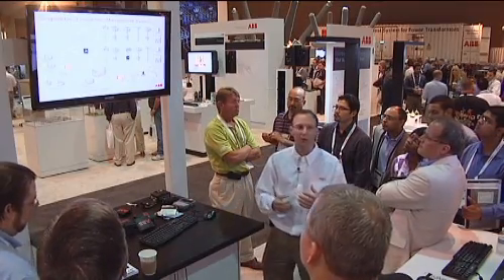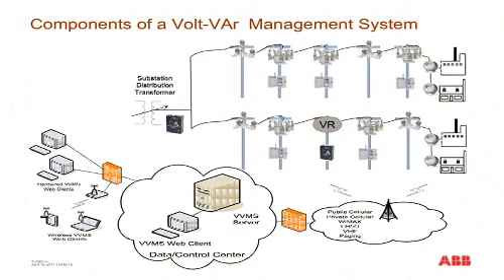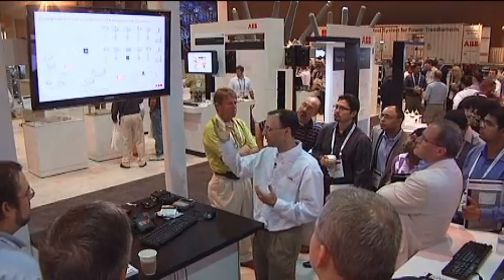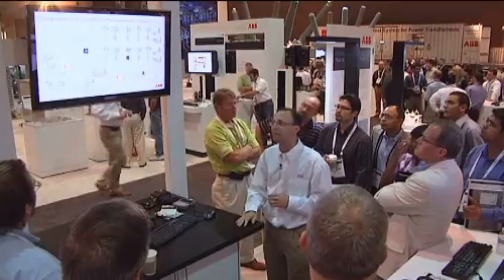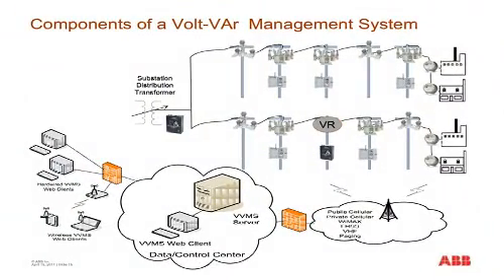And then, as I mentioned earlier, for conservation voltage reduction, we're really trying to push the envelope of the voltage low, and we're only doing that at high peak demand times, but we're trying to push that as low as we can. We need better sensing to make sure we're not violating that voltage. So we can put additional sensors along the poles. At each cap station, we have sensors there that we're monitoring, but in addition to that, we can put sensors on poles, and then we can utilize automatic meter reading, and at selected customers, we can utilize the information obtained from those meters. So typically along the feeder, maybe 4 or 5 key customers will monitor those meters and make sure that we're not violating those, but that's giving us an overall view of the whole feeder.